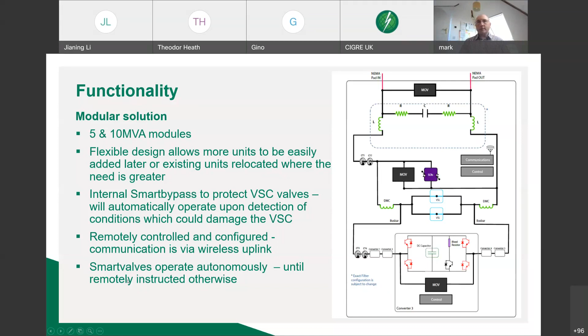There are a couple of other key points to note here. This technology is wirelessly controlled. It's autonomously controlled, in that there's control on board the devices, but there is no hard wiring to the unit. So you remove one of the traditional challenges, the potential difference between control systems that are at ground and those at system voltage, because these units float at system voltage. If we look at how an installation typically sits, these installations sit at system voltage, and these units are just connected in series.